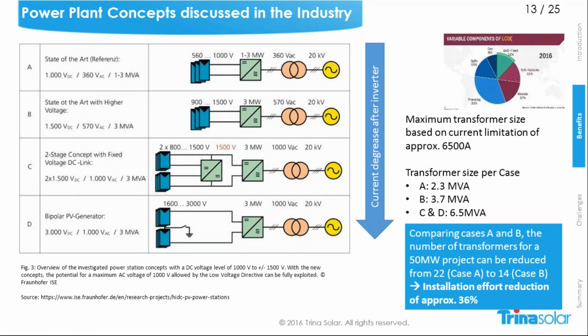If you now take a look at the transformer, transformers are usually limited by the maximum current. In this example, it's 6,500 amperes. For sure, this depends on the manufacturer. If you take the 6,500 amperes and check the different cases, in case A the maximum transformer size will be 2.3 megavolt ampere. In case B with the 1500 volt system, it will already be a size of 3.7 megavolt ampere. That means you need fewer transformers per project. In cases C and D, where we have a much higher output voltage, the transformer size can be up to 6.5 megavolt ampere.